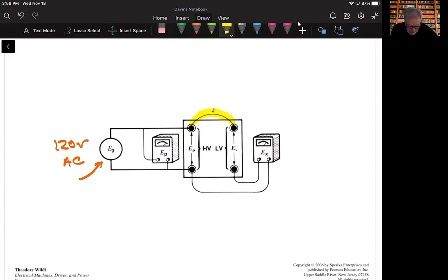Now we're going to take a jumper and connect it between any two adjacent high voltage, low voltage terminals. We could have gone from here to here, or from here to here. Either one of those would allow us to perform this determination.